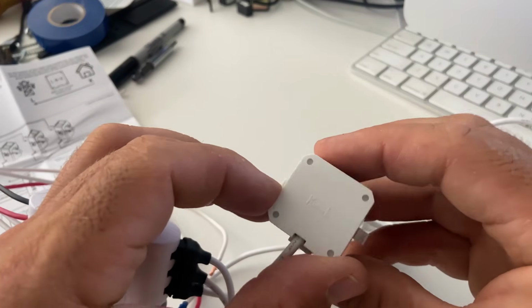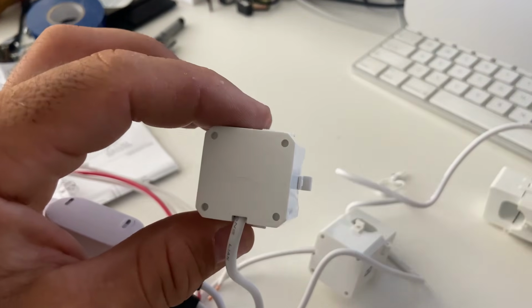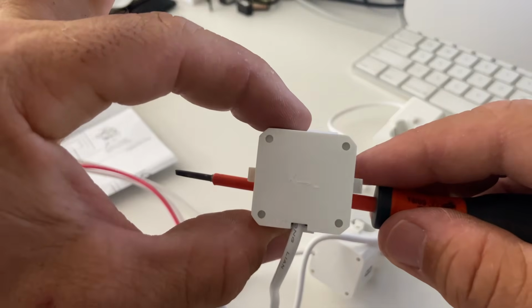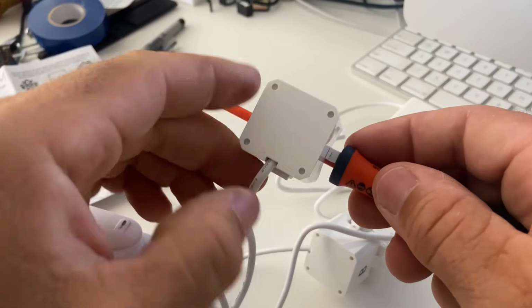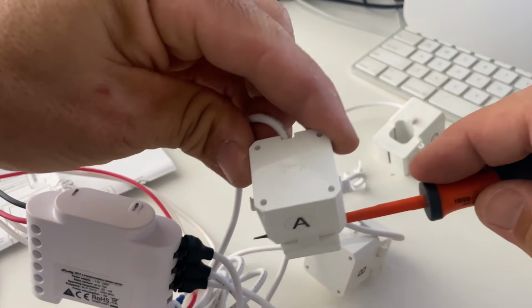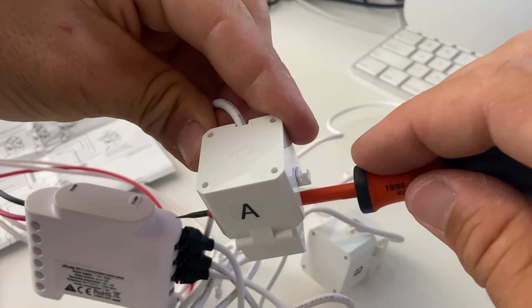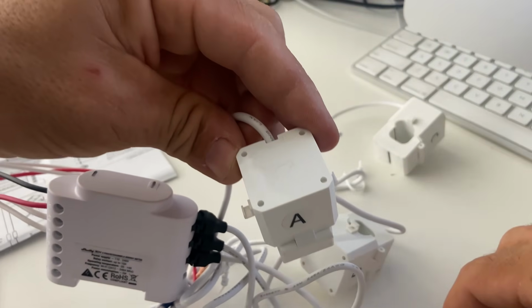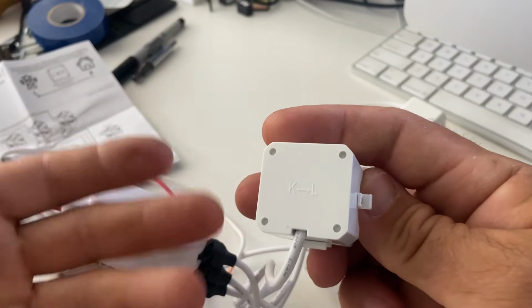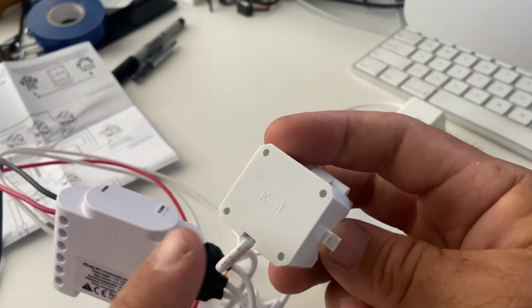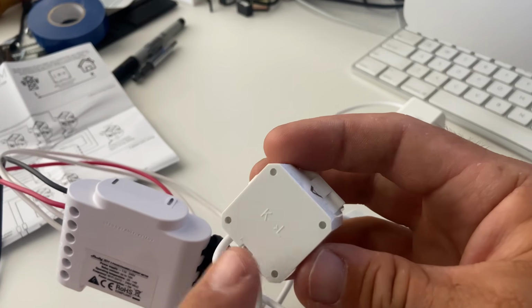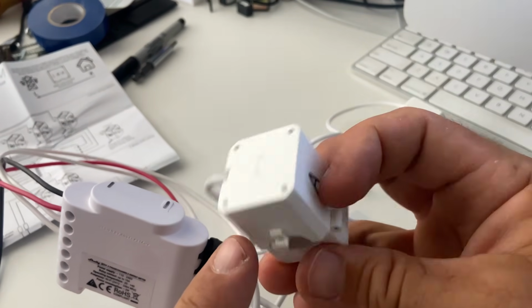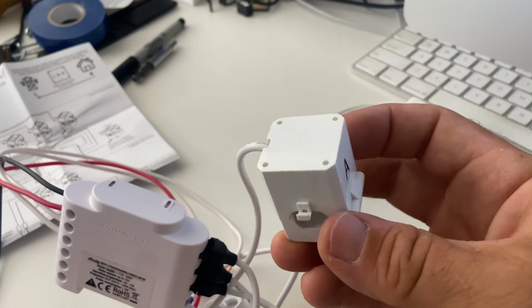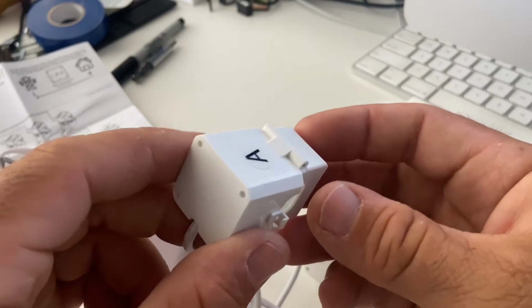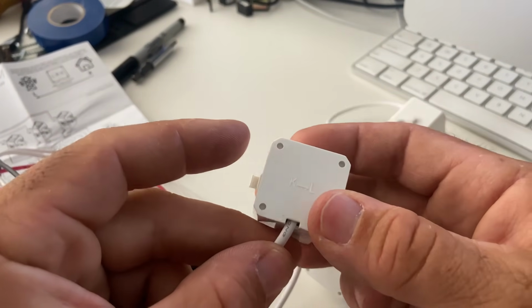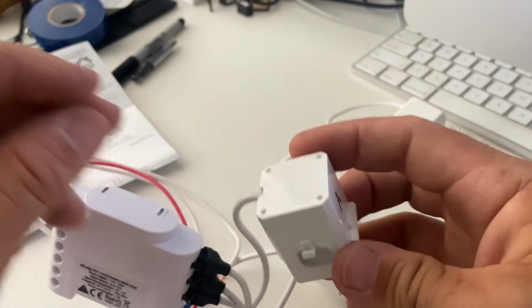These have a little marking to show which way to clip it onto the wire. So depending on which way the wire goes through the CT, it will either show negative or positive current - this way or that way the wire will pass through. If you get it wrong, all you have to do is flip it around and then you'll be in the positive. One other thing I found is if there's a solar system producing power, to work out which way around it goes, it's easier just to flick off the solar system while you're doing it, and then turn it on and check that the current is all going in the positive, so you know you've got it the right way around.